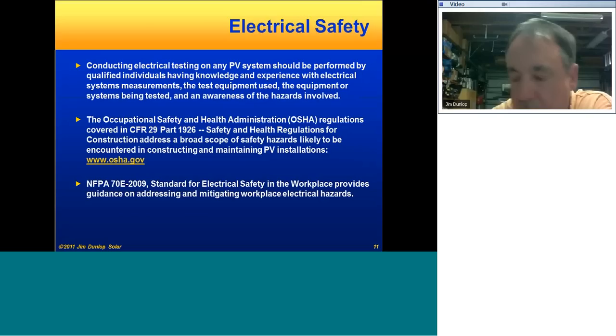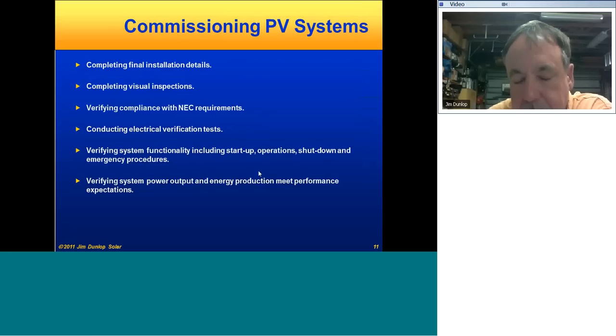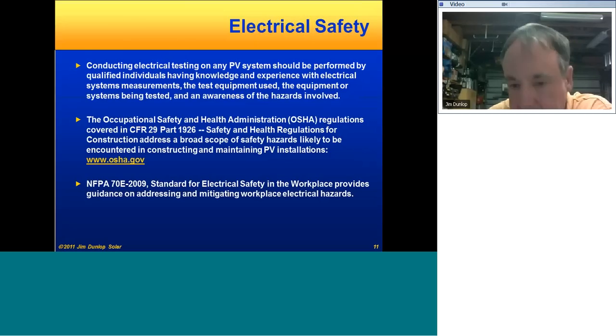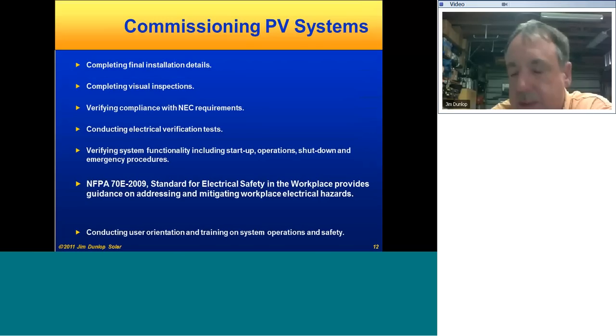Otherwise, they're going to have an appreciable arc flash boundary associated with larger systems, and it's going to require a lot of full arc flash suits and personal protective gear, and we've got to work on these things if you want to follow all the rules. So that's part of the engineering of the systems, to try to make that a little bit less significant in terms of arc flash potential at those combiner boxes or any points in the DC system.